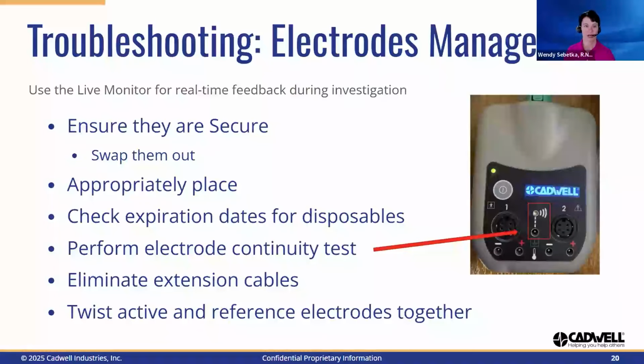The electrode continuity test is performed by plugging the electrode into the isolated ground input and placing the metal electrode on the metal pole just above the input. If the electrode is good, an audible tone will play and the lights on the amplifier will change from white to blue. Noise occurs due to an increased potential difference along the circuit. Removing extension cables reduces the amount of available surface area. Likewise, twisting your recording electrodes together decreases the distance between the poles and eliminates additional opportunities for infiltration. The next items to consider are environmental factors.